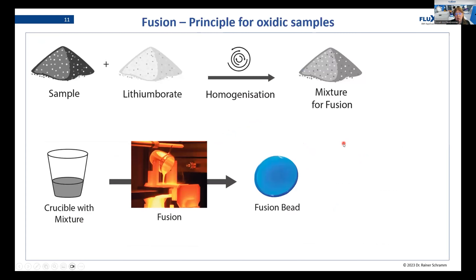For completely oxidized samples, the process is also quite easy. Similar to the pressed pellet — though the fusion process takes longer and you need another machine — in general you mix the sample with some glass-building material, which in most cases is a lithium borate, you homogenize it, then you have your mixture for the fusion, everything together in a crucible, then fusion, fused bead, and done.